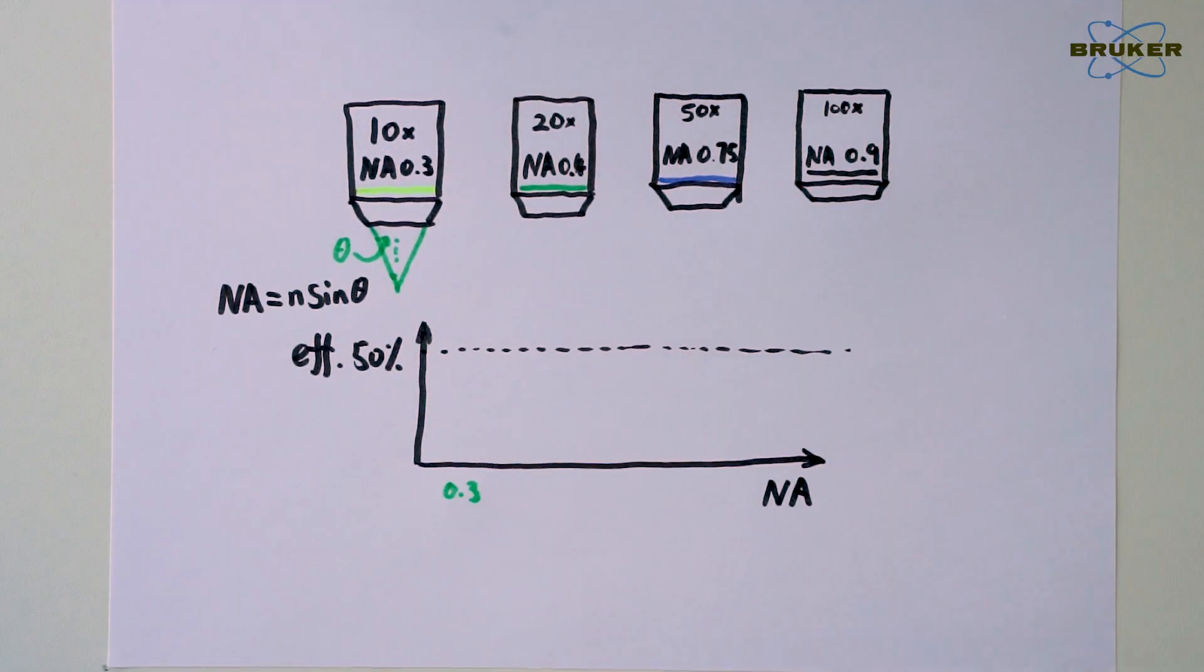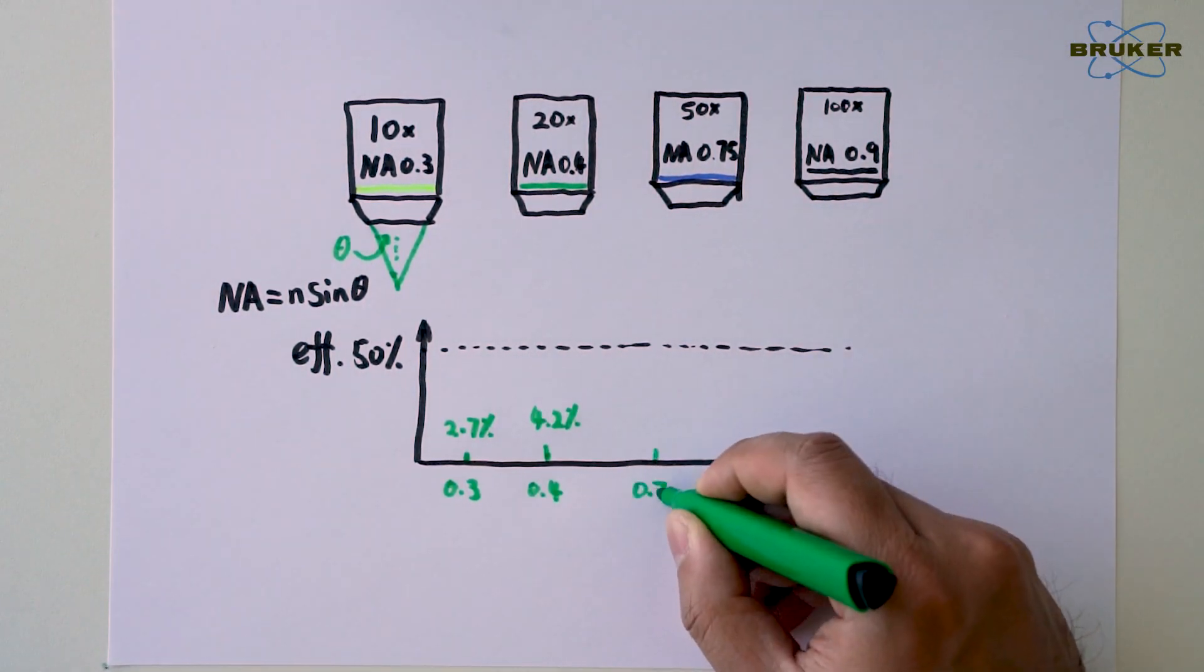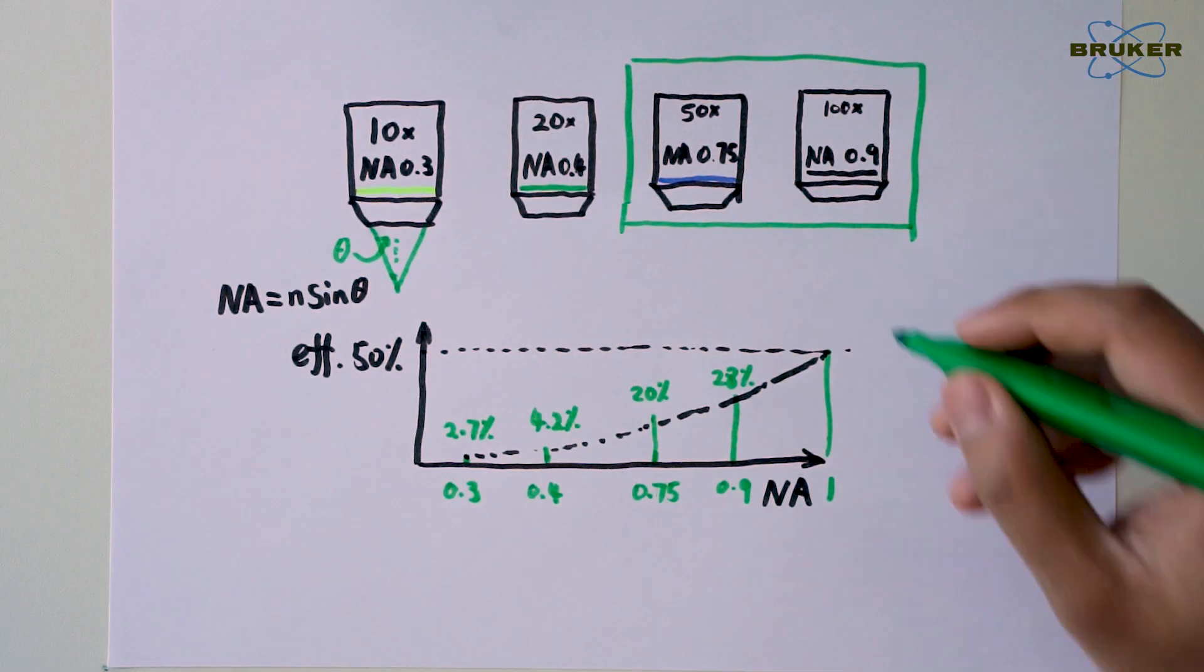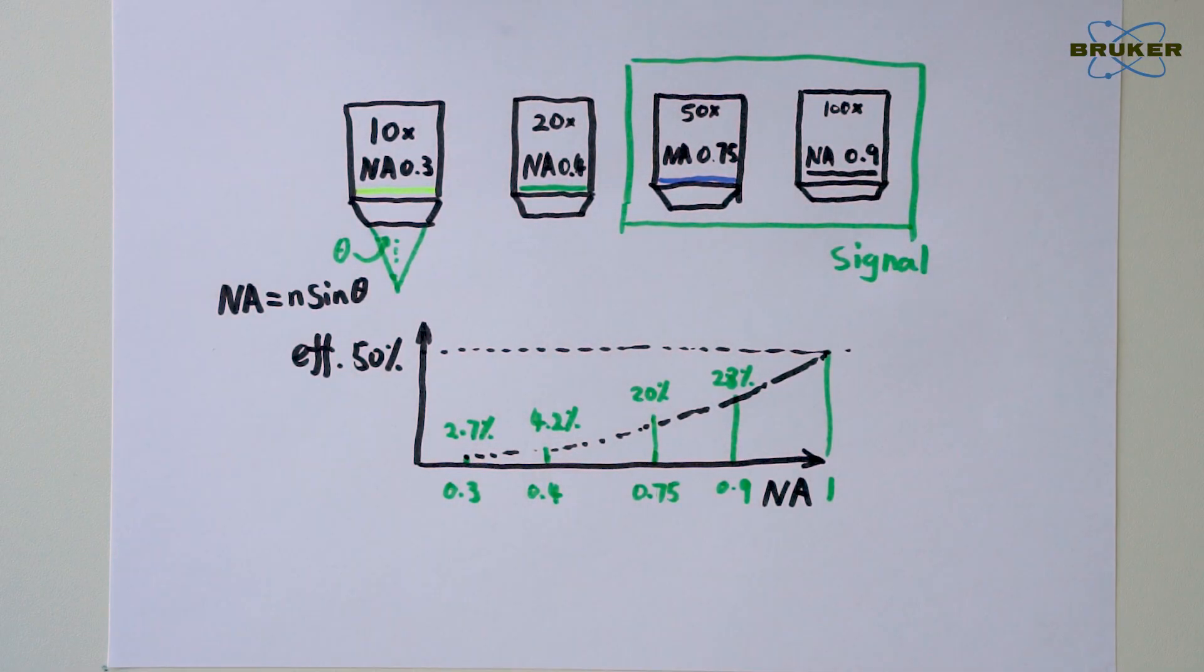These four can collect 2.3%, 4.2%, 20% and 28% respectively. Clearly, we choose objective lens with high NA for the best collection of Raman signal.